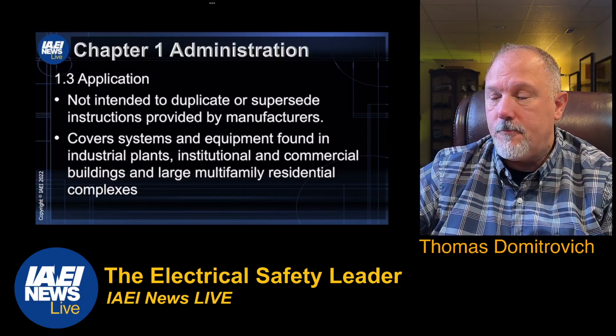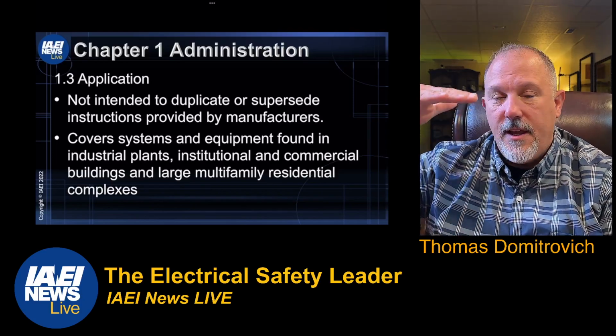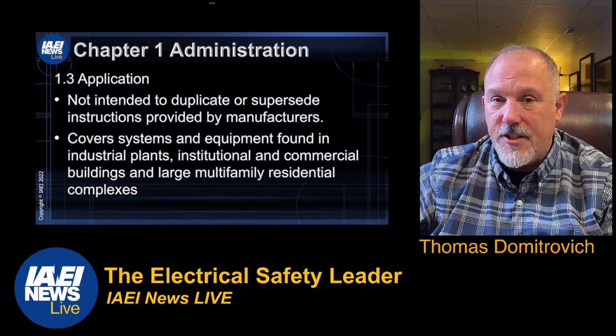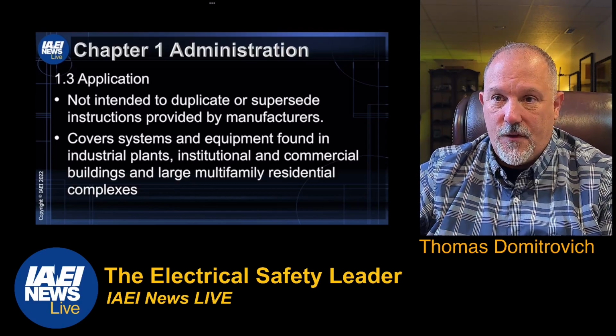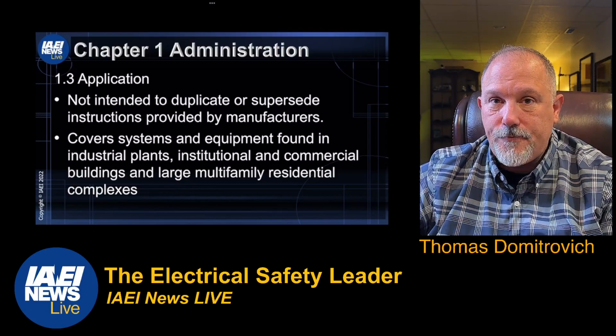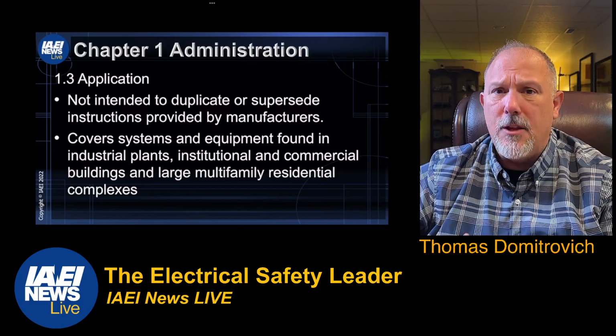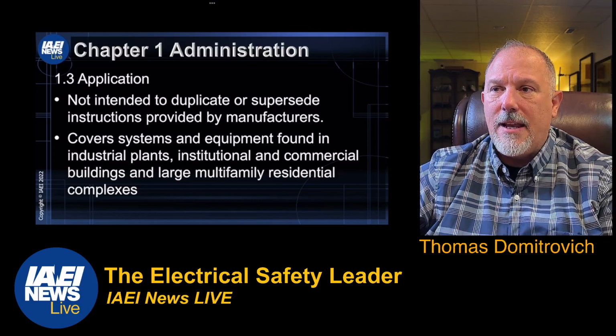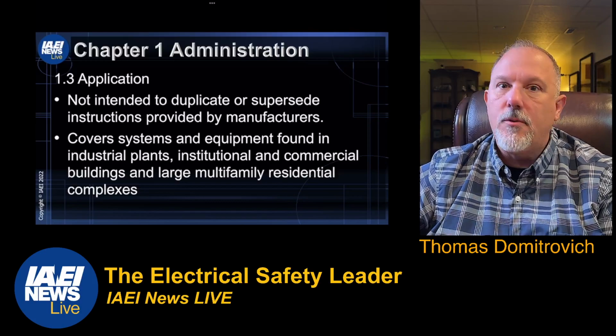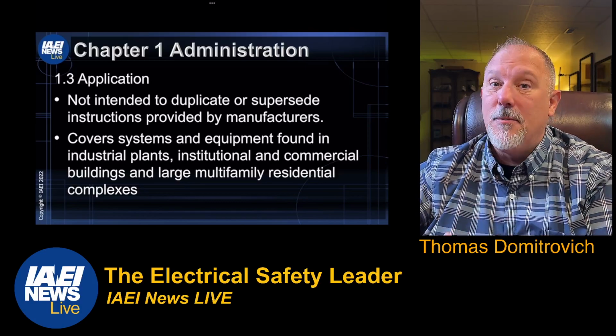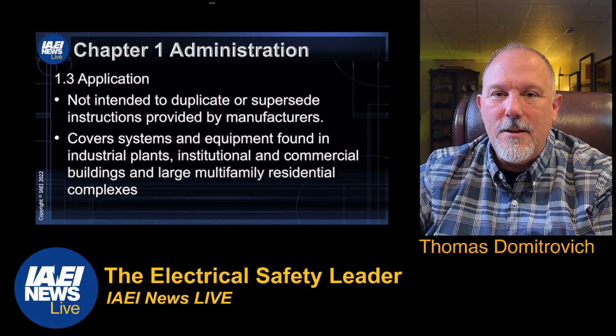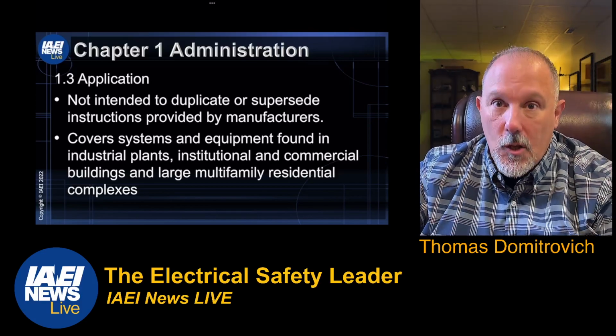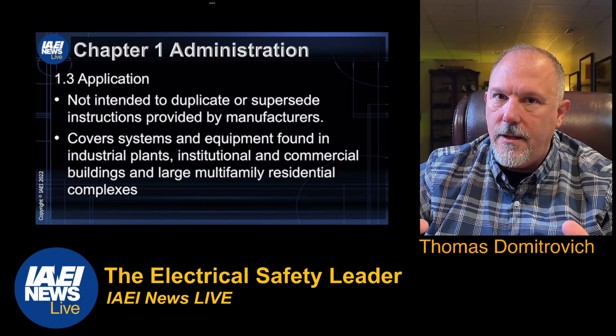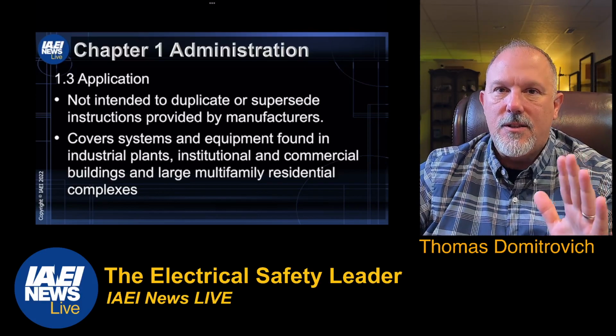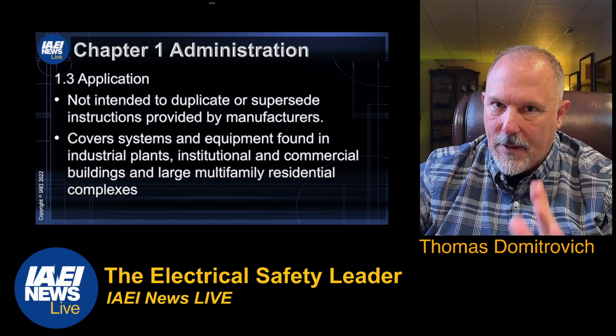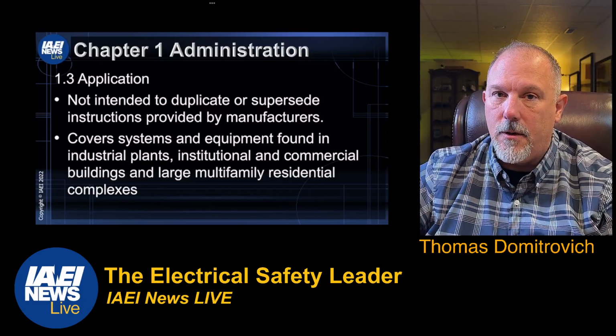But honestly, if you look through the list of all the different chapters—if you're looking at maintenance of a receptacle, receptacles are found in many locations. If you're looking at maintenance of a panel board, a load center is a panel board, it's a residential panel board. We call it the 'load center,' but that's a marketing term only, not a technical term, not how it's listed. It's listed to the panel board standard, so it is a panel board.